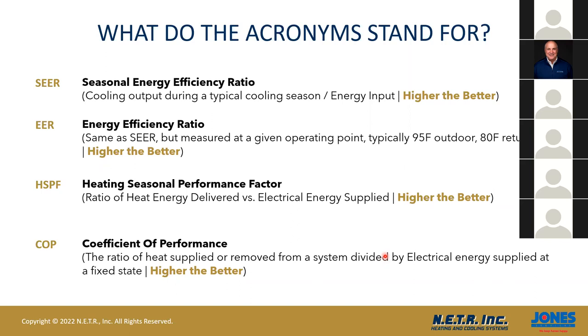So now the COP, the coefficient of performance that I showed you earlier. This is the ratio of heat supplied or removed by a system divided by the electrical energy supplied at a fixed state. This is the COP where the manufacturer rates their unit at certain temperatures. Okay, so the higher the COP at certain lower temperatures, for example 5 degrees, the better. When you look at different manufacturers or different units that you're buying, the higher the COP, the better, the less it's going to cost to operate.